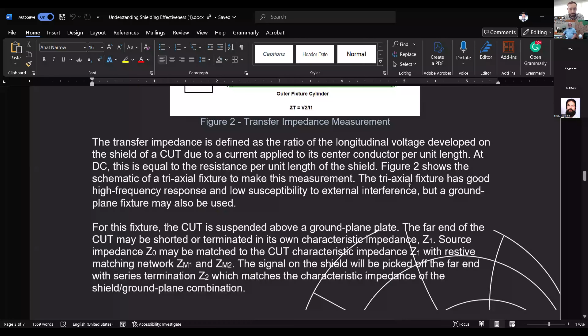Shielding effectiveness is another thing you do, up to higher frequencies. Here you have this complicated fixture. The reason it's complicated is because you're trying to measure what's going on the shield, and there's not supposed to be anything there. So you have to invent a triaxial fixture and this outer enclosure. There are ways of measuring shielding effectiveness, and this is basically how it's done.